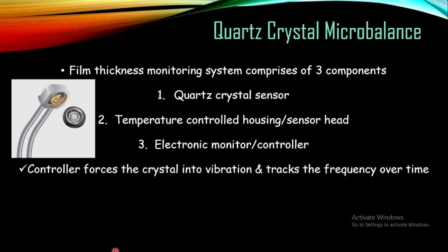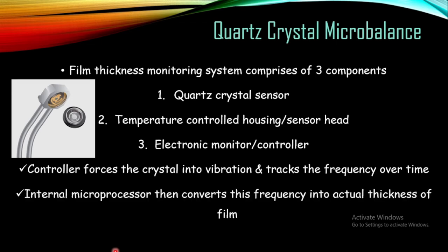The controller forces the crystal into vibration — the quartz crystal starts vibrating — and simultaneously monitors and tracks the frequency of vibration with respect to time. A small voltage stimulus makes the quartz crystal vibrate, the frequency is recorded at different times, and an internal microprocessor then converts this frequency into the actual thickness of the film using a formula or software.